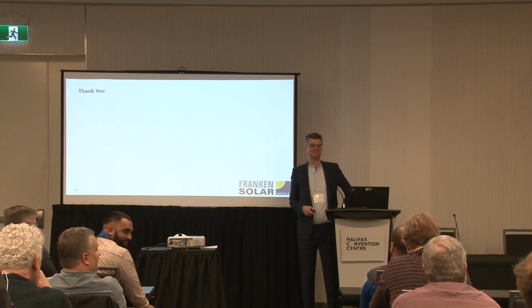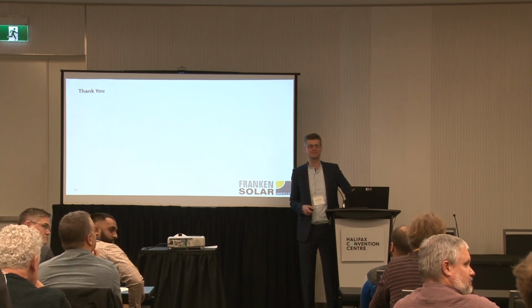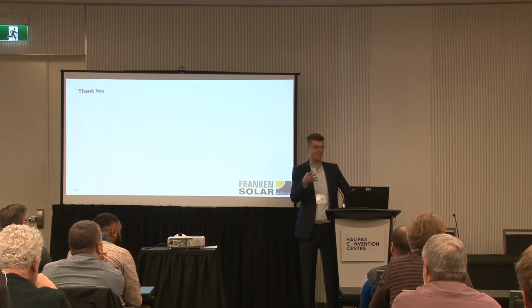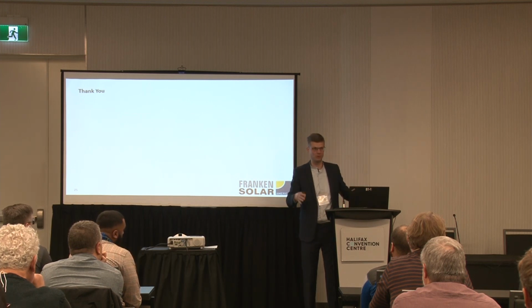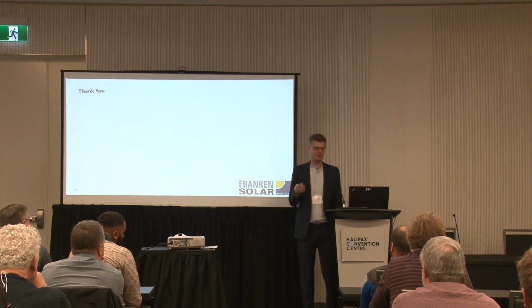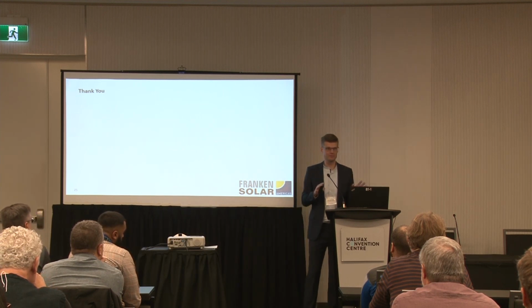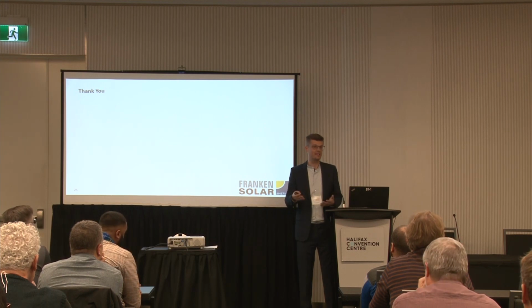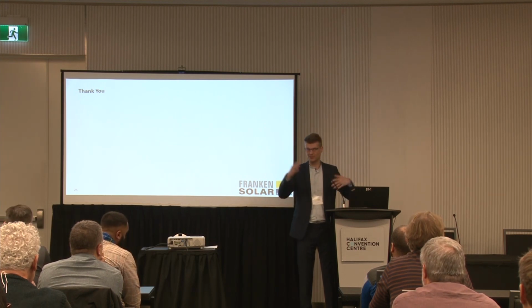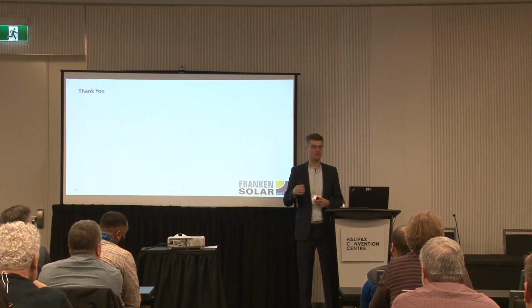Yeah, go ahead. Have you done a study with the DC to AC ratio that you originally did with bifacial modules instead? So bifacial modules act like a higher DC to AC ratio because you have some gain, whatever much that gain will be, from the backside. It's very, very hard to simulate bifacial because none of the software solutions are really on point to quantify bifacial, because there are so many factors that go in and you cannot rely on, let's say, an STC flash test, no matter if it's a front flash test or a back flash test in addition. So it's mainly, from an engineering perspective at the moment, just a ballpark number.